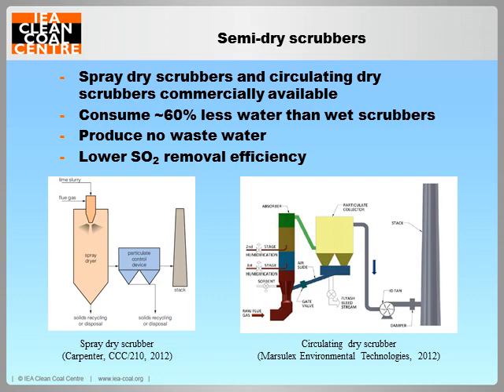Right, looking at semi-dry scrubbers, there are two main types that are commercially available. These are the spray dry scrubbers, that are also known as spray dry absorbers, and circulating dry scrubbers, these are also called circulating fluidized bed scrubbers. Right, the water consumption of these two types of scrubbers is similar, and they consume about 60% less water than wet scrubbers. They also produce no wastewater, unlike the wet scrubbers, so no water treatment system is required.